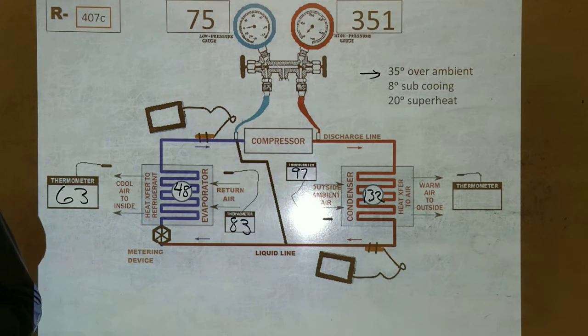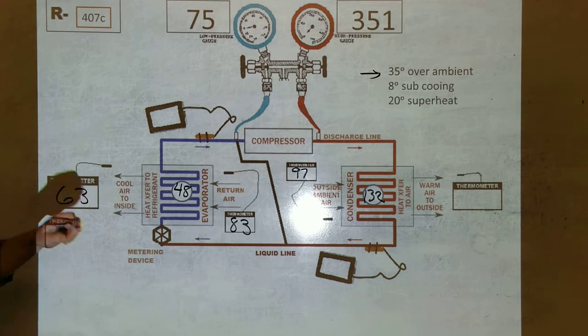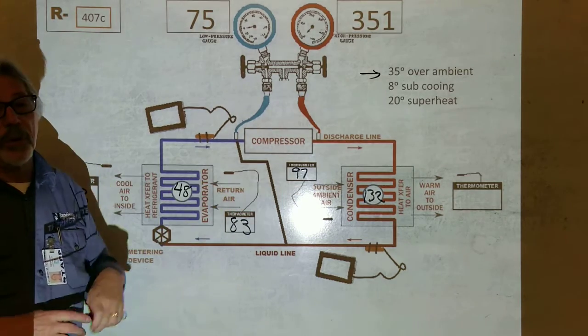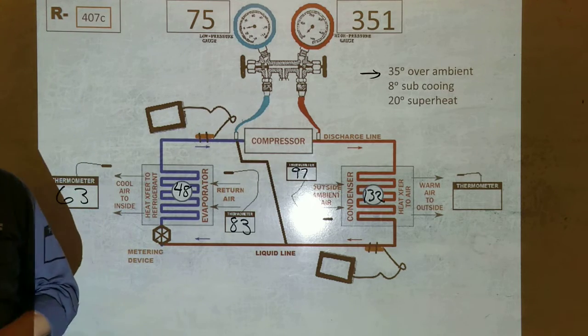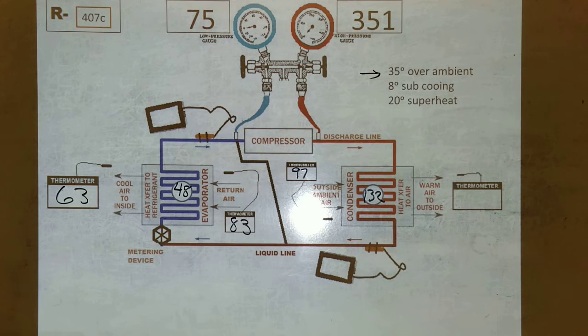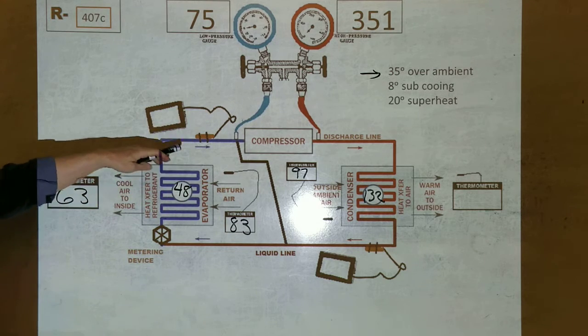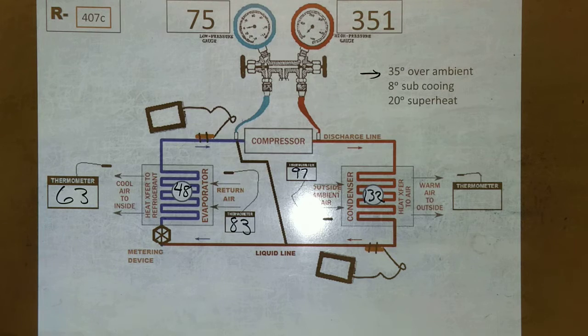Years ago, what we would do is add 35 degrees to the ambient on every single air conditioner, and we'd be right where we're supposed to be. But since they started making high efficiency units, they changed the size of that condenser coil, and now it's lowered the pressure and lowered the temperature. So now we have different subcoolings for different units. A unit that is over 40 years old, you can still go 35 degrees over ambient. But you gotta know that that unit's over 30 years old. This could be a unit that's over 40 years old, 45 years old, because 407 is a replacement refrigerant for R22. So you could have 35 degrees over that ambient if it's an old unit.